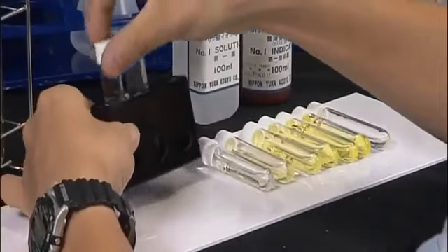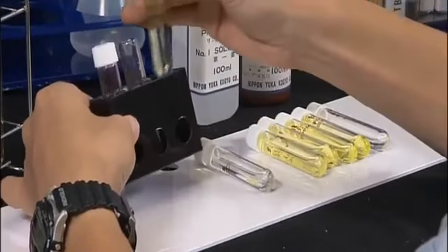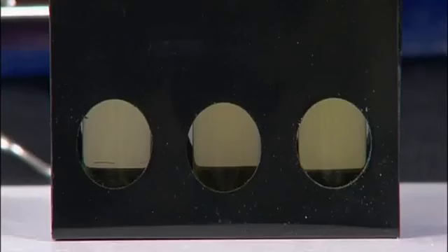Choose a couple of reference ampoules of the closest tints and put them together with the sample into a comparator dark box. This allows you to identify the reference ampoule color corresponding to the sample and find its value, which is the phosphate ion ppm.